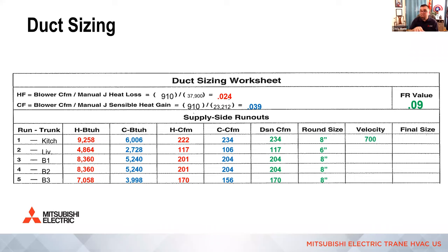Now, if we get to designing around minimums, when it comes to supply, like in the kitchen here, if I have a short run, I'm okay with designing around 700 feet per minute. If I have a long run, I don't want to have that pressure loss down the run and lower velocity by the time it hits the register. So I would downsize that run if it makes sense and I'm not going to be above the max. So in this example, I might keep it an 8-inch if it's short. If it's going to be long, I would see, if I go down to a 7-inch, what's that volume of air going to give me? And is it above the maximum? All right. Because we can't go above 900 in that example.